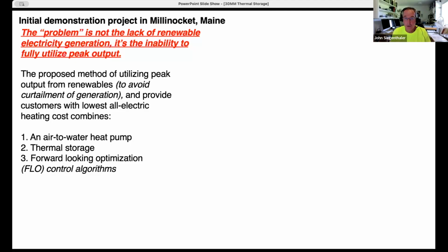This is where there's a great opportunity, especially with these wholesale rate structures and the 48-hour advance forecasting—that's point number 3 on the slide: forward-looking optimization. This is where we use a computer with a pretty sophisticated algorithm that, knowing the next 48 hours of pricing on an hour-by-hour basis, determines our best operating mode right now. Should we run the heat pump? Should we draw from thermal storage? And so forth. Of course, it's a dynamic situation, so calculations are always being done to determine what we should do next.